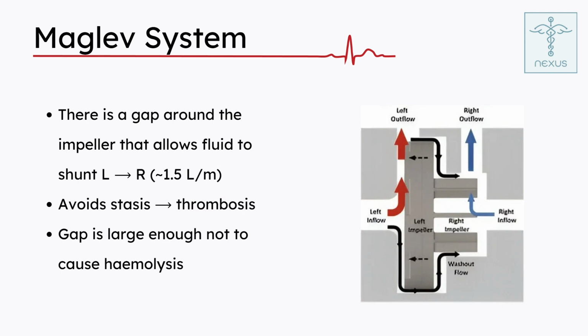That's 1.5 liters per minute flowing around the sides. The output of the left and right sides should be the same, about 5 to 6 liters normally for a human, and this device can range anywhere from 3 to 12 plus liters per minute. But there's an additional 1.5 liters per minute going from left to right.